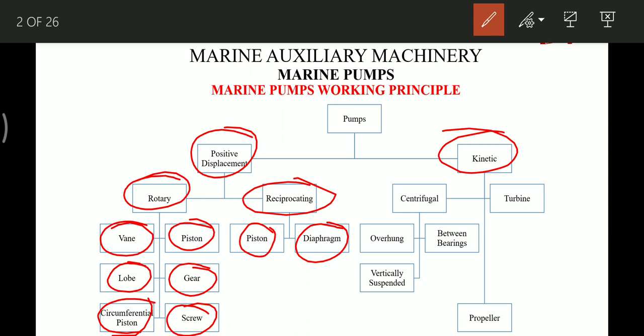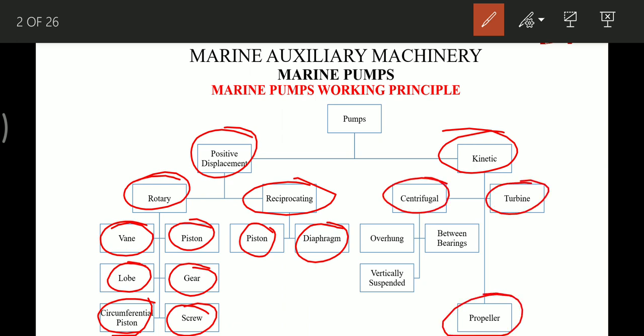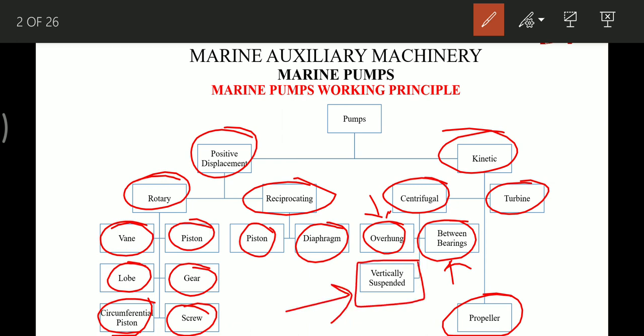Coming on to rotodynamic or kinetic pumps, these are broadly classified as centrifugal pumps, turbine pumps, and propeller pumps. Centrifugal pumps are further divided into overhang or between-bearings types — between-bearings means the impeller is supported between two bearings, while overhang means it is supported from one side only — and vertically suspended pumps. The majority of pumps in the engine room, whether sea water or fresh water cooling pumps, are vertically suspended.